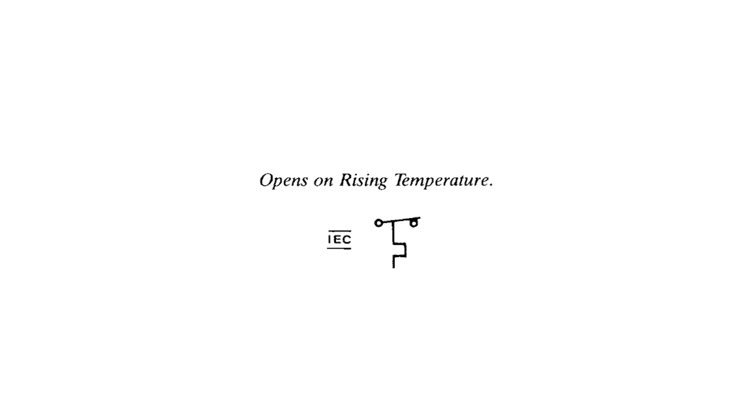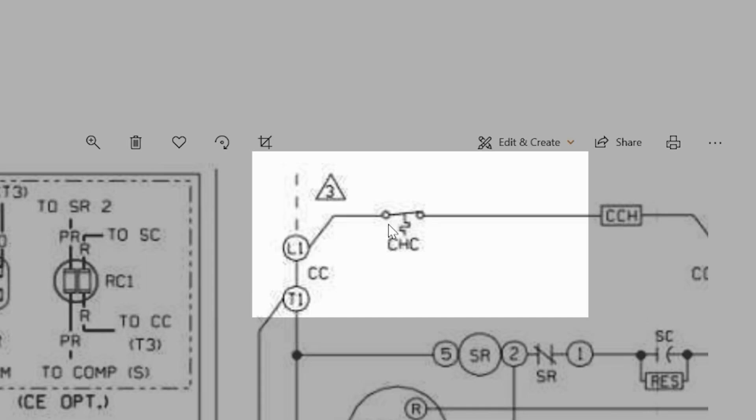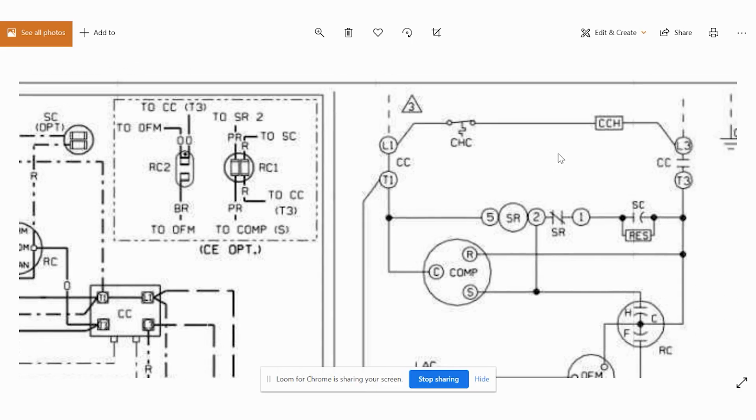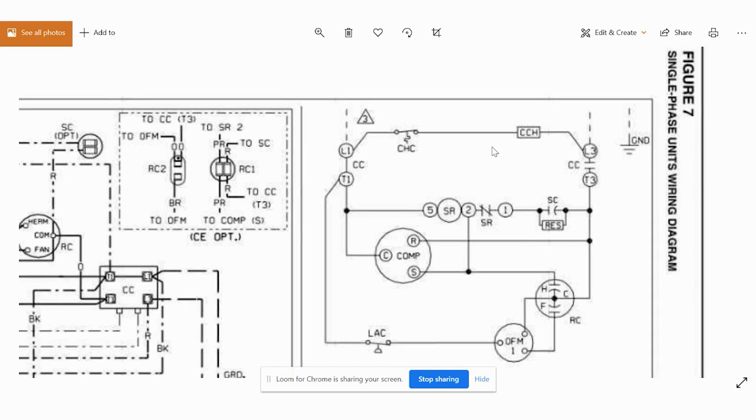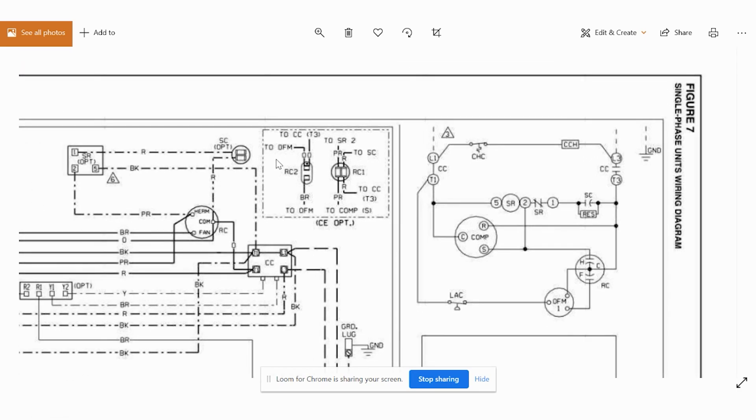The way that this looks, where it's kind of a squiggly line underneath, this is a thermal switch. So if this crankcase heater control is low enough temperature, then it will make the circuit and allow our current to move through our crankcase heater. So that's how that would be wired. But we don't know by looking at the ladder side or the schematic side that that is optional.